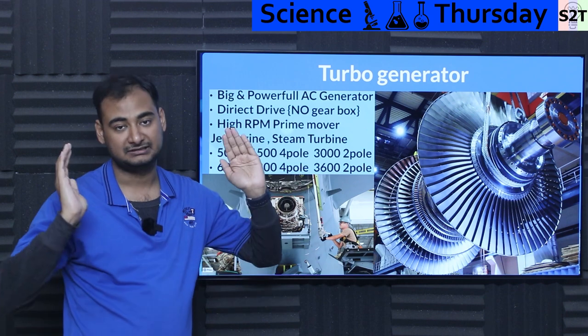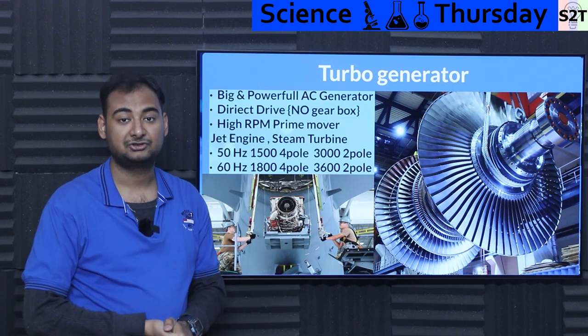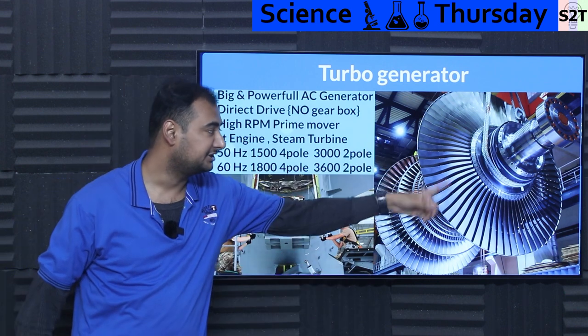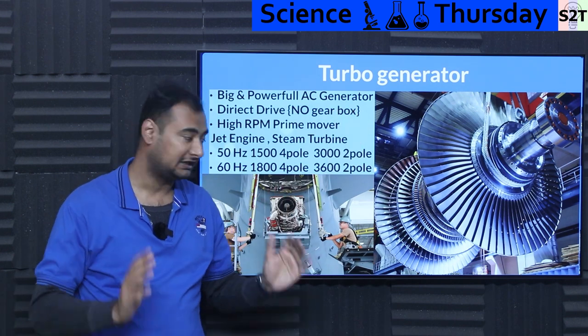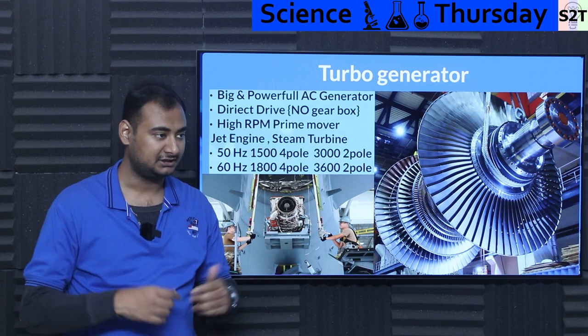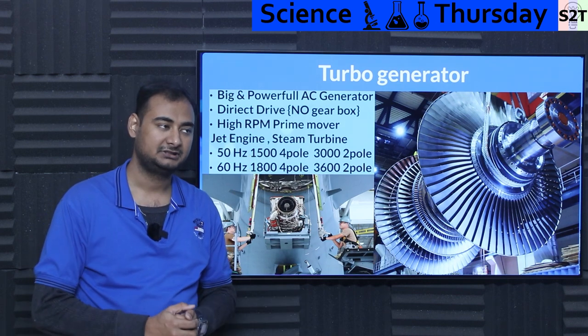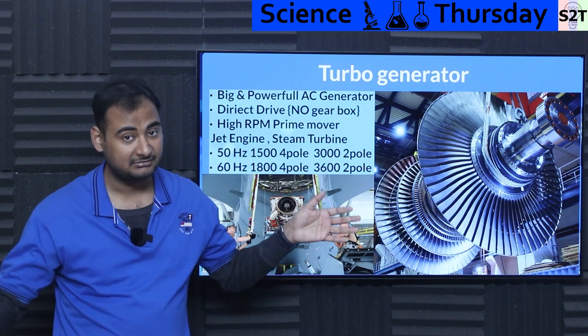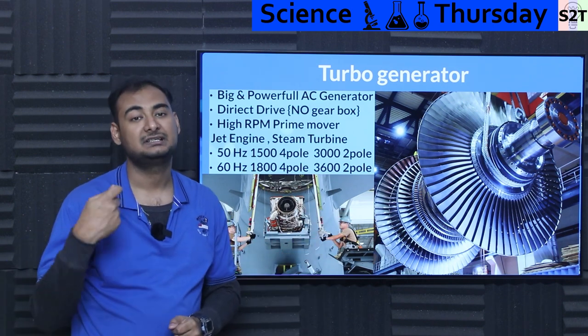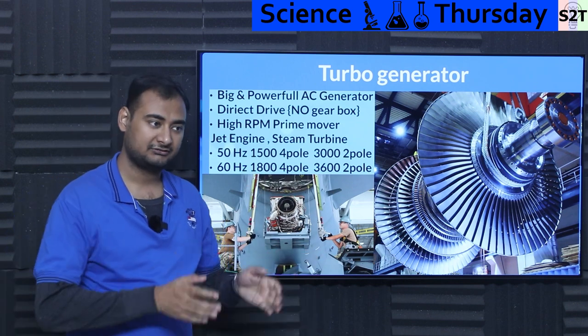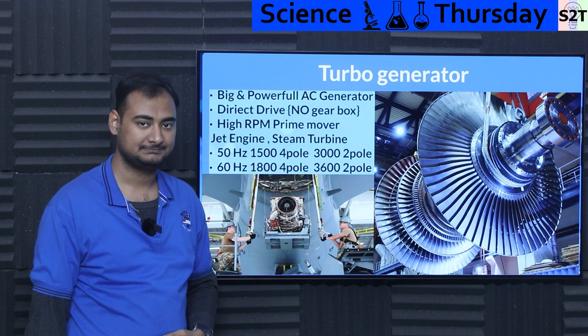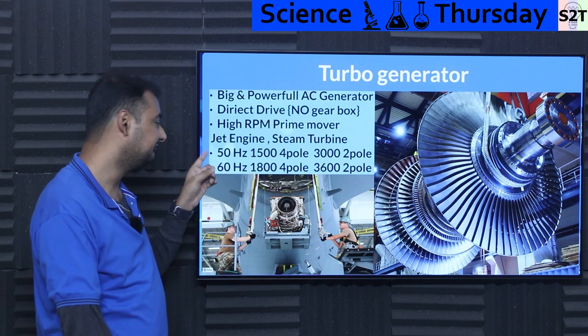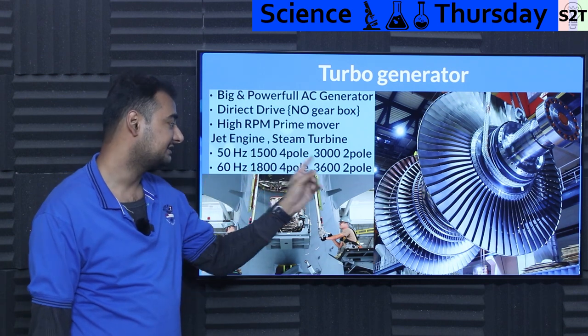If the manufacturer says the biggest turbine we can ship is limited to 10 meters in diameter, and you need more output — you can't transport more turbines or make them bigger — you can increase the RPM, going to a two-pole system. Conversely, if you have very low RPMs, you can increase the pole count and still get 50 Hz. At 60 Hz, you need 1800 RPM for four poles, or 3600 for two poles.